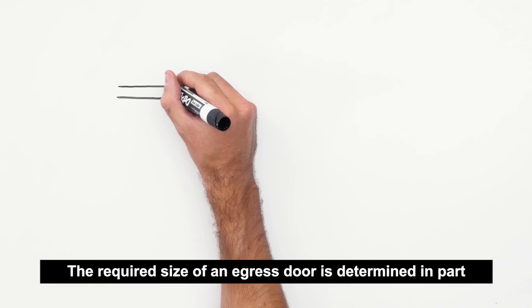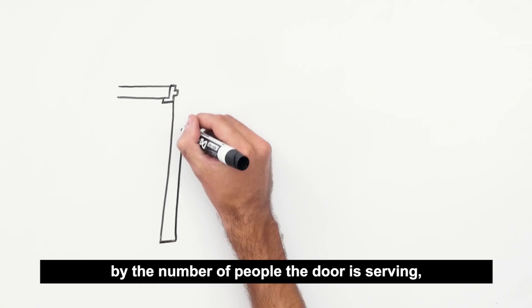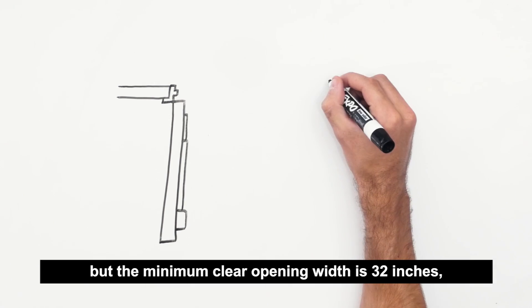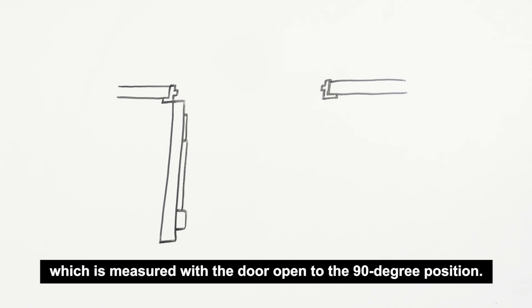The required size of an egress door is determined in part by the number of people the door is serving. The minimum clear opening width is 32 inches, which is measured with the door open to the 90 degree position.